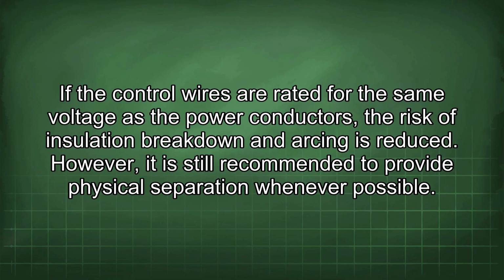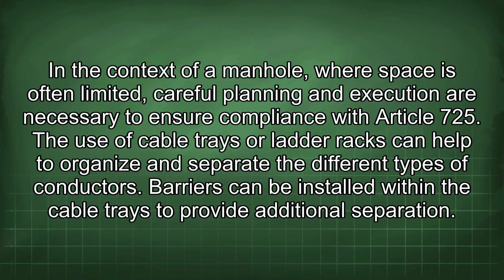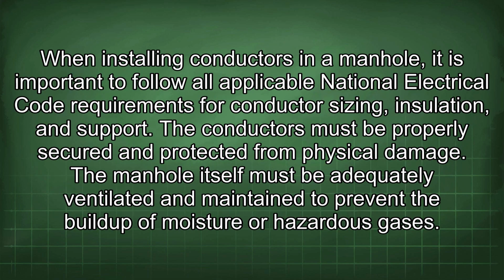If the control wires are rated for the same voltage as the power conductors, the risk of insulation breakdown and arcing is reduced. However, it is still recommended to provide physical separation whenever possible. In the context of a manhole, where space is often limited, careful planning and execution are necessary to ensure compliance with Article 725. The use of cable trays or ladder racks can help to organize and separate the different types of conductors. Barriers can be installed within the cable trays to provide additional separation. When installing conductors in a manhole, it is important to follow all applicable National Electrical Code requirements for conductor sizing, insulation, and support. The conductors must be properly secured and protected from physical damage. The manhole itself must be adequately ventilated and maintained to prevent the buildup of moisture or hazardous gases.